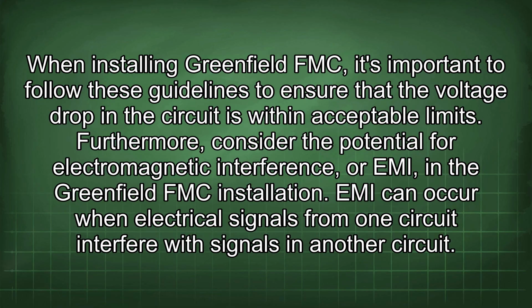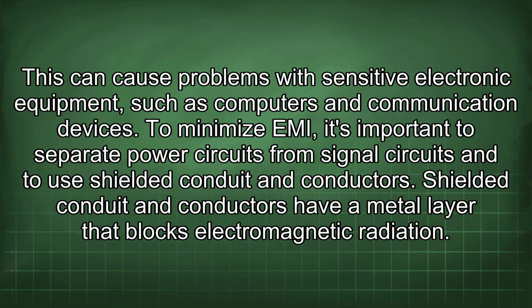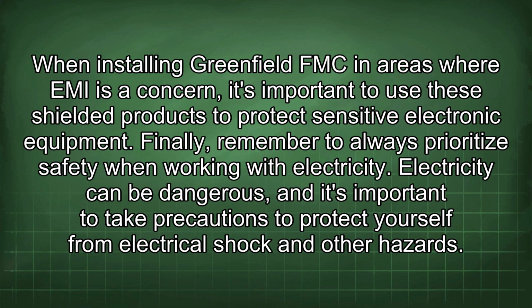Furthermore, consider the potential for electromagnetic interference, or EMI, in the Greenfield FMC installation. EMI can occur when electrical signals from one circuit interfere with signals in another circuit. This can cause problems with sensitive electronic equipment such as computers and communication devices. To minimize EMI, it's important to separate power circuits from signal circuits and to use shielded conduit and conductors. Shielded conduit and conductors have a metal layer that blocks electromagnetic radiation. When installing Greenfield FMC in areas where EMI is a concern, it's important to use these shielded products to protect sensitive electronic equipment.